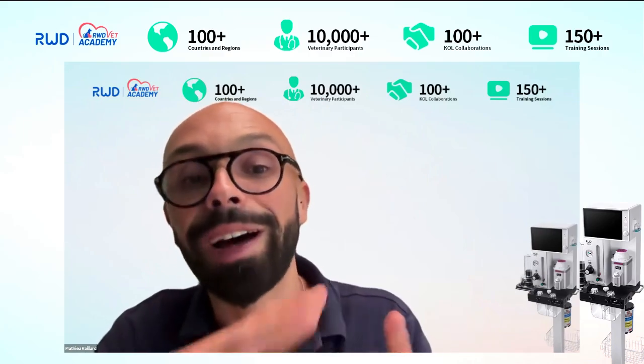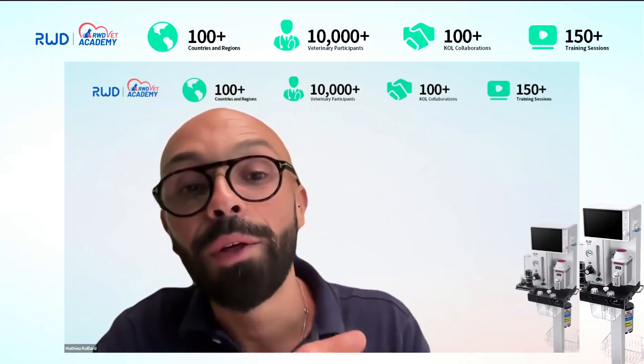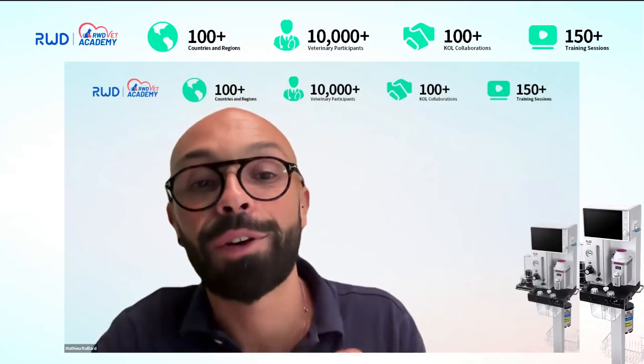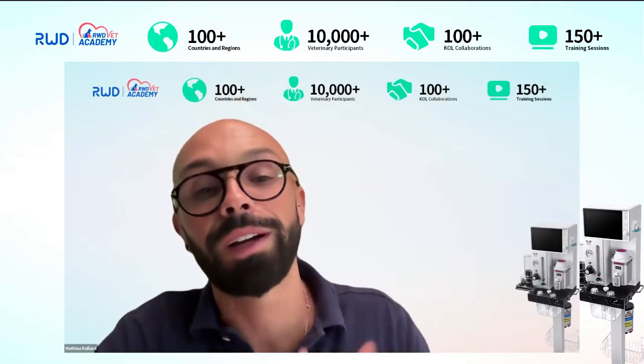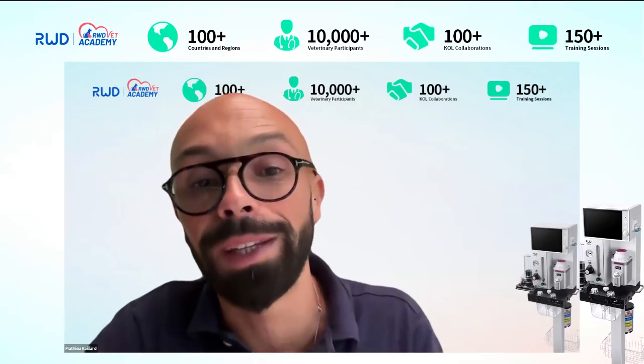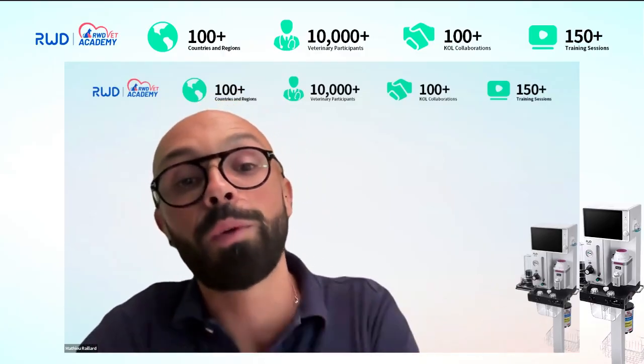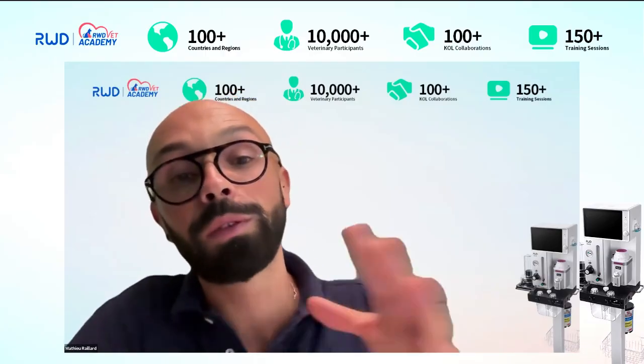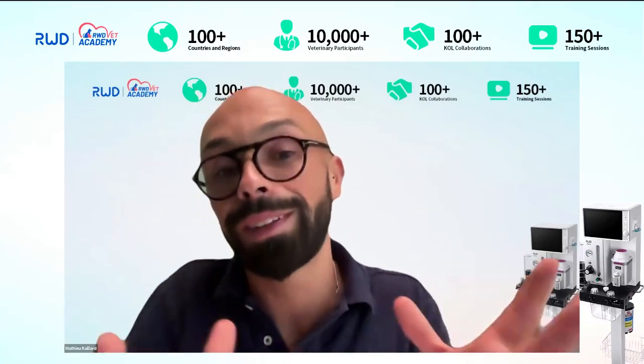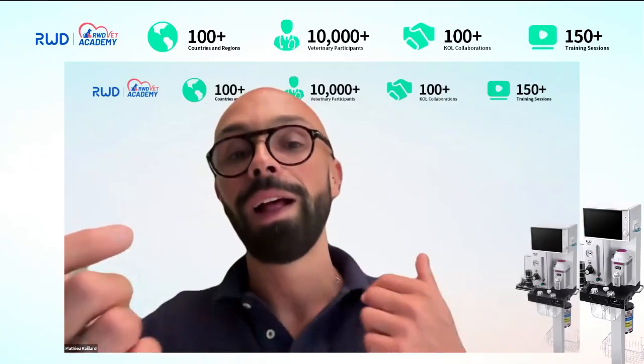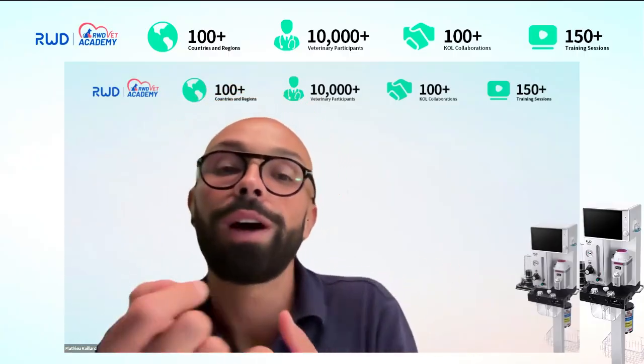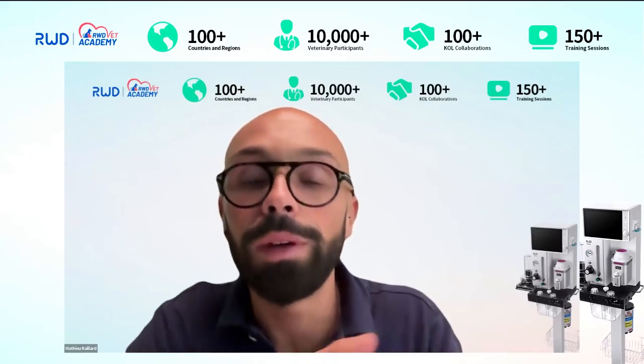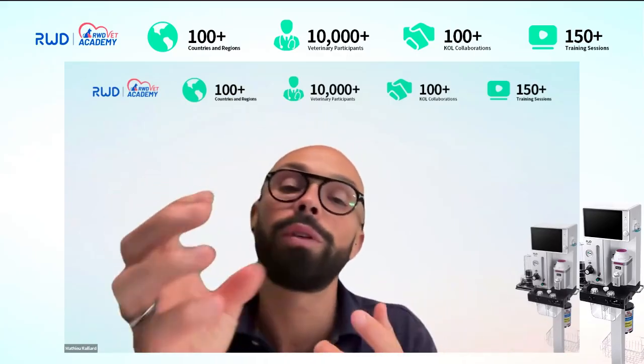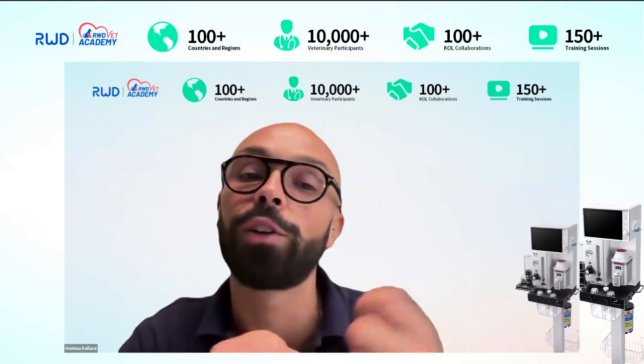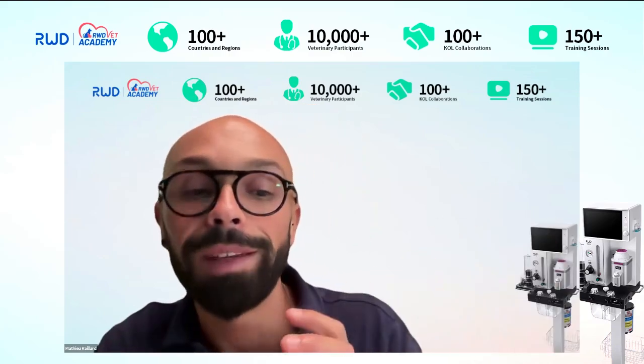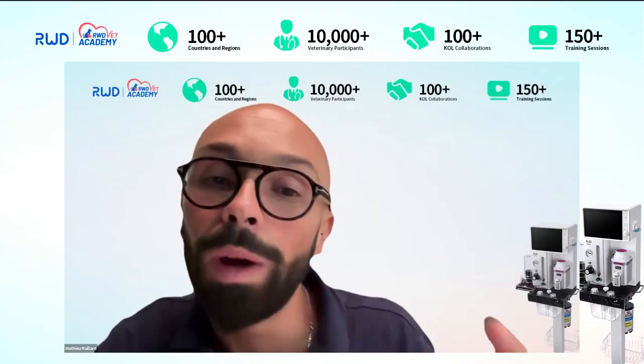An anesthesia ventilator has been developed around the use of volatile anesthesia and therefore the use of a plenum vaporizer. And you cannot use high fresh gas flow in an anesthesia ventilator because otherwise your vaporizer will not cope with it. So our systems are designed to recycle the gases, and therefore, as opposed to an ICU ventilator, you have a very low flow in a normal anesthetic system, and your movement is given only by the ventilator or by the animal that moves. And that makes everything with more resistance and way slower.